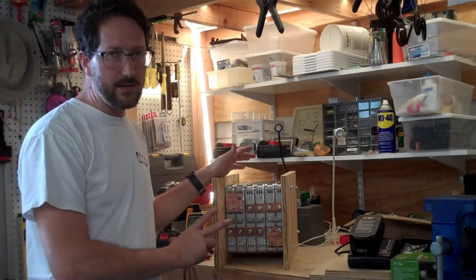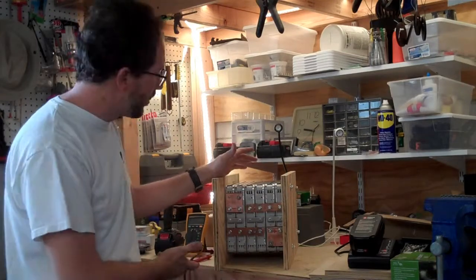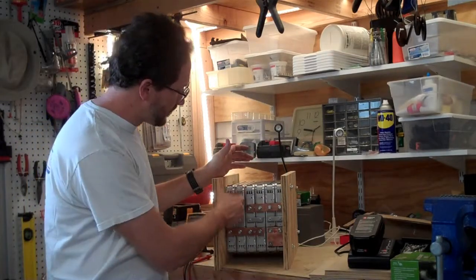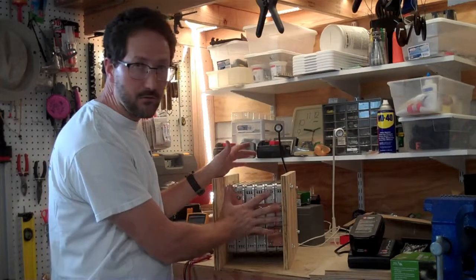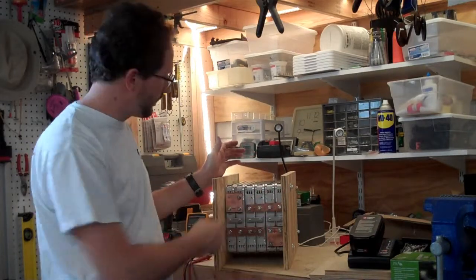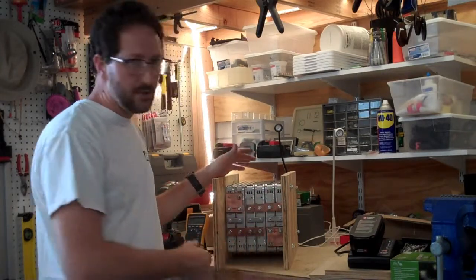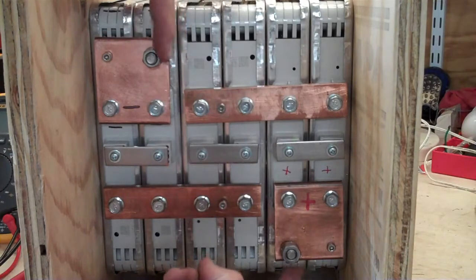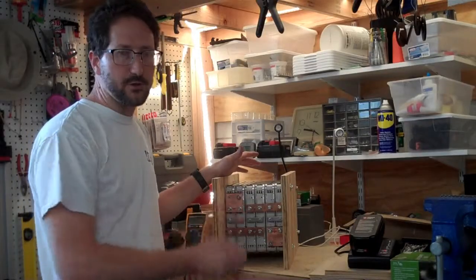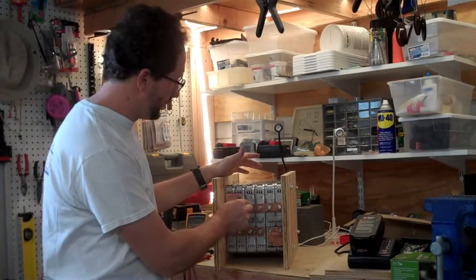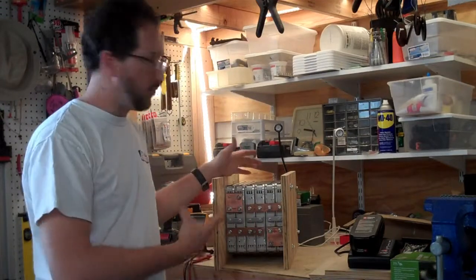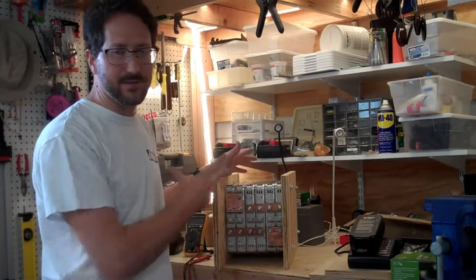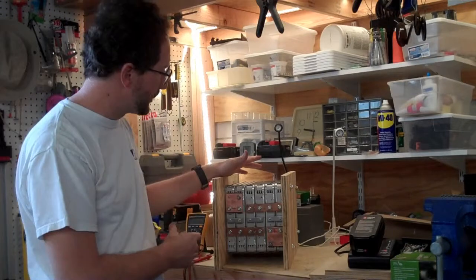and it's separating 8 volts at hundreds of amps. So we're going to be putting some spacers between those and a cover over the top to cover pretty much everything except the main lugs for the main high current output. That way, if somebody were to drop a wrench or a screwdriver, it wouldn't span a couple of bus bars and spot weld itself, and then just have a short circuit in there.